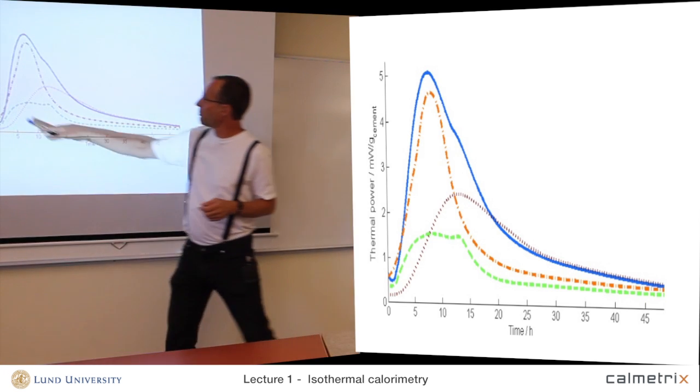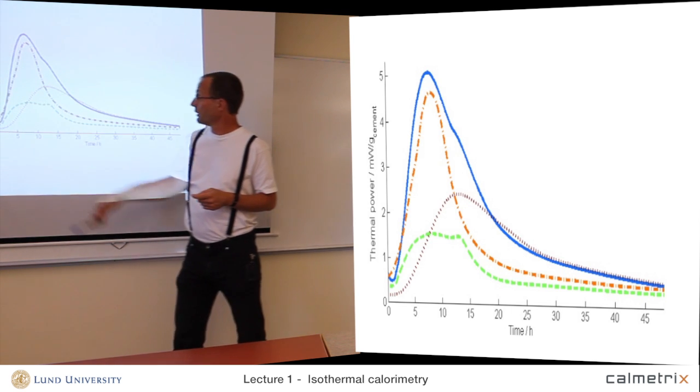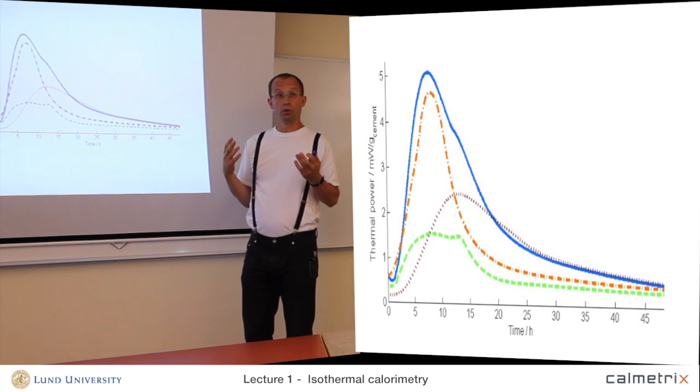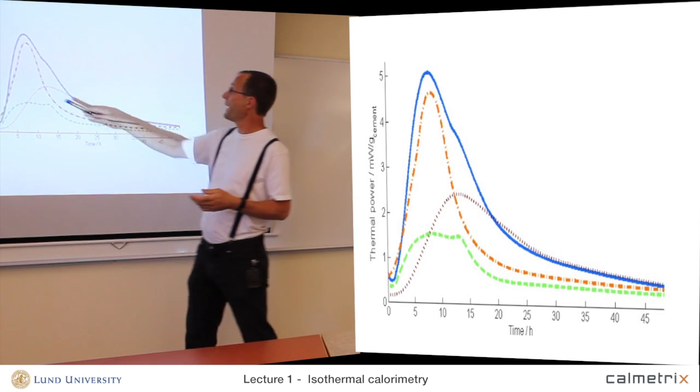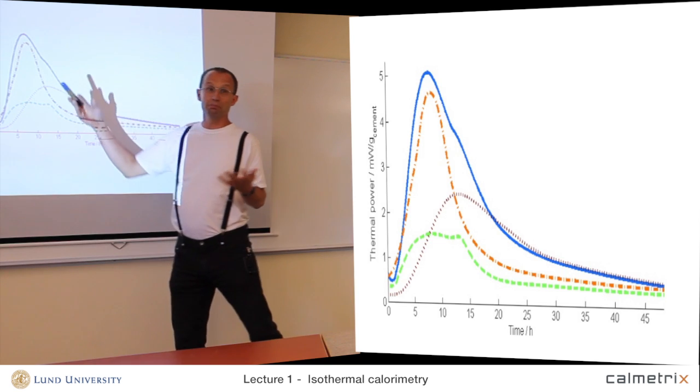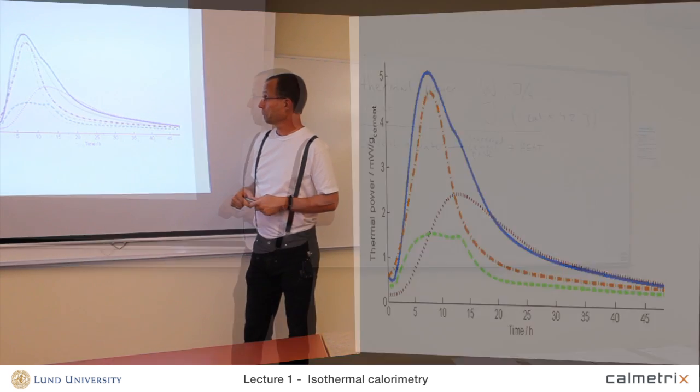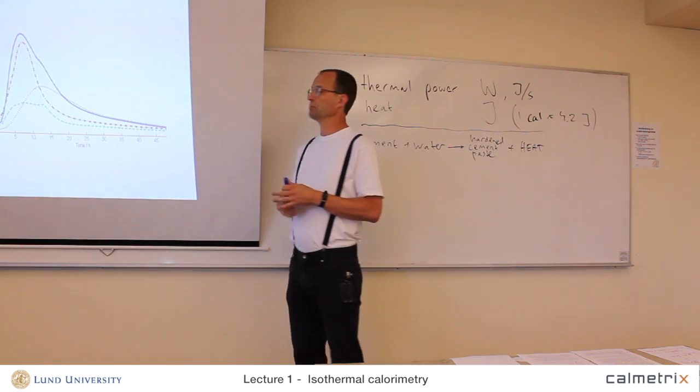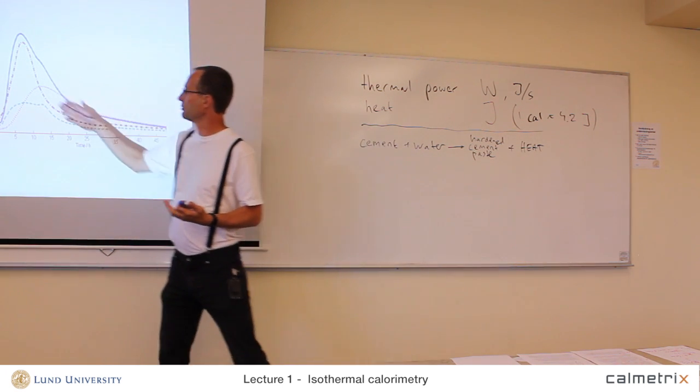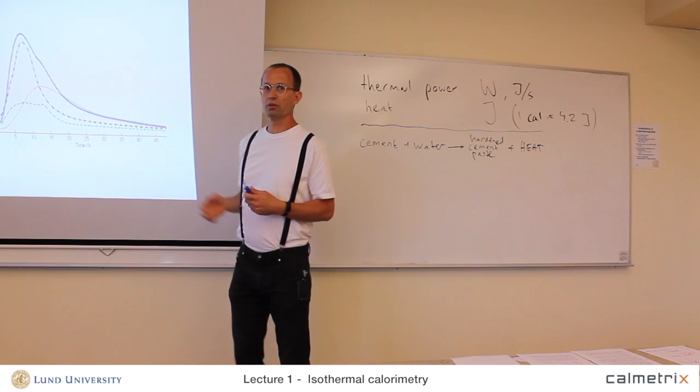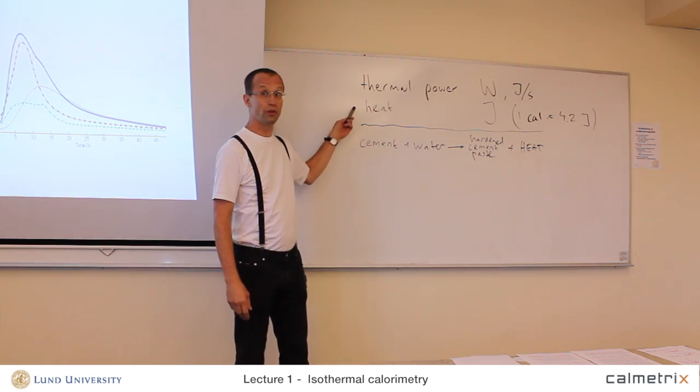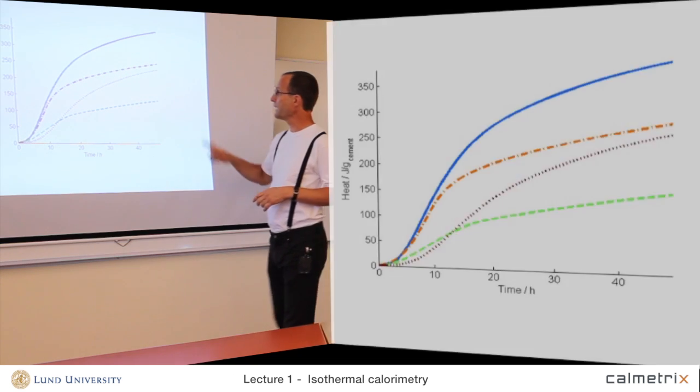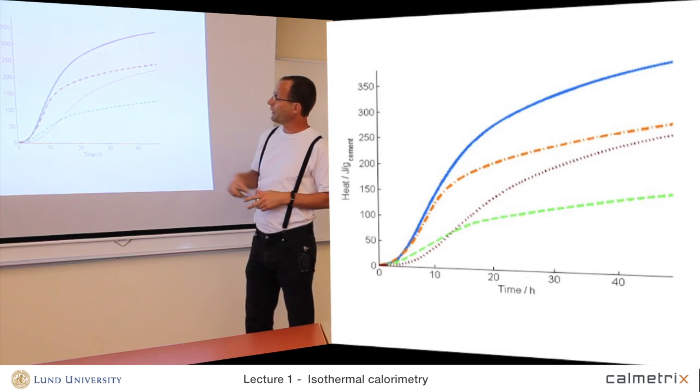As I said earlier, we have the thermal power, milliwatts per gram cement here. That's very typical that we scale with the mass of the sample, because then we can compare different samples that have different masses. So this is thermal power, this is the primary measurement variable, this is what we get out from the calorimeter. If we integrate this, we will get the heat, and I can show you the heat here too, the same process, the same curves.